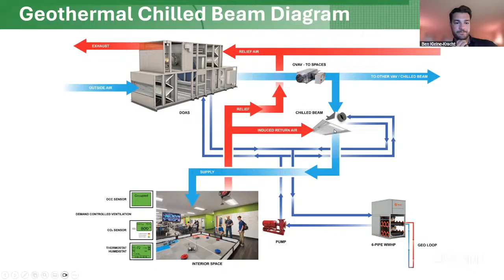Here's a typical chilled beam classroom layout. You have 5 to 6 of these in each room, and you can see the control valves and the layout in this right-hand corner. But again, they're nice and clean - they look like a diffuser, they smell like a diffuser, but they're not a diffuser. It's its own terminal unit. This air is coming from a DOAS, so this is raw outside air that's been conditioned, and then it's provided to each of those terminal units.